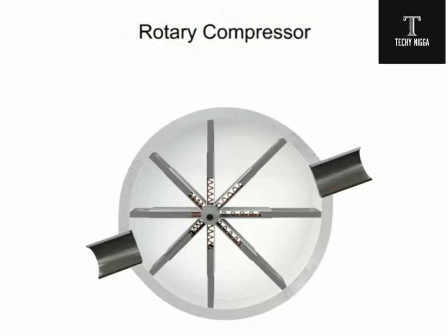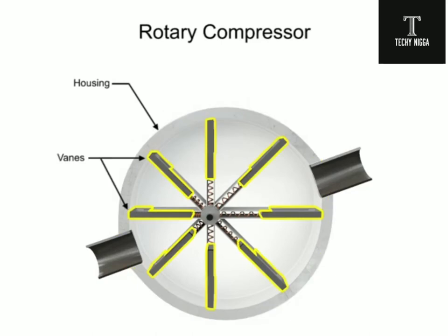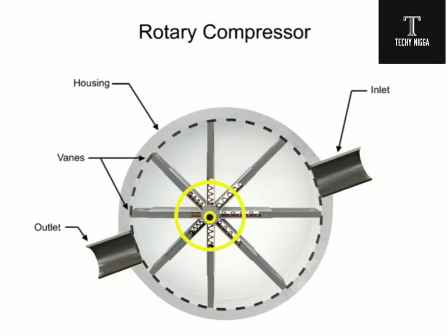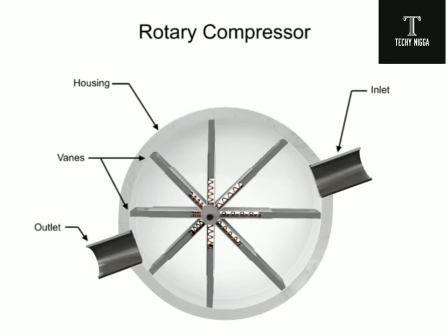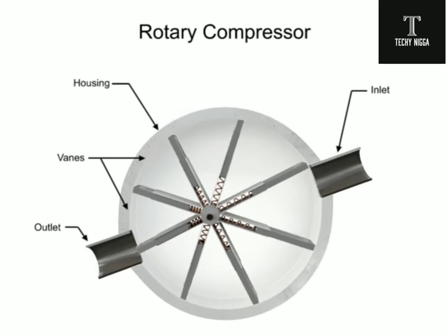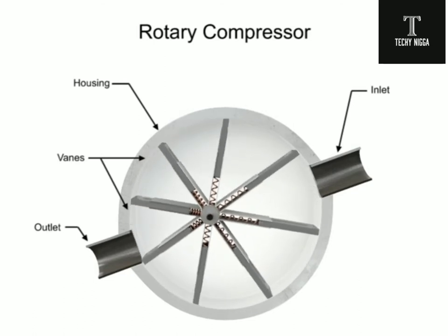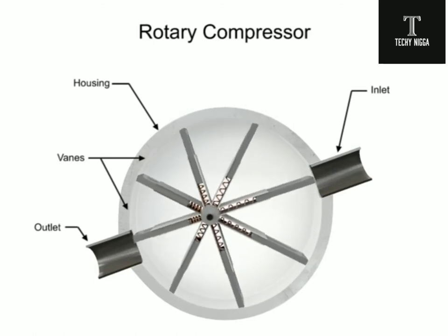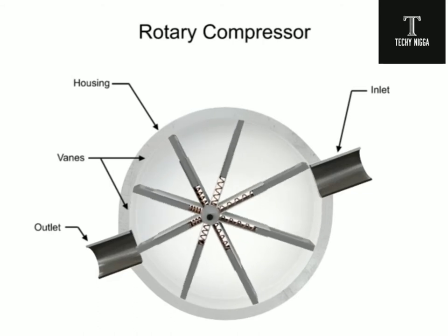Rotary compressors typically consist of a cylindrical housing with adjustable rotary vanes, an inlet, and an outlet. The vanes are on an off-center drive shaft. As the shaft rotates, the vanes slide in and out to maintain contact with the cylindrical compressor wall.